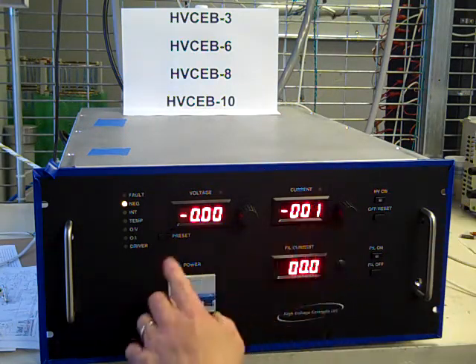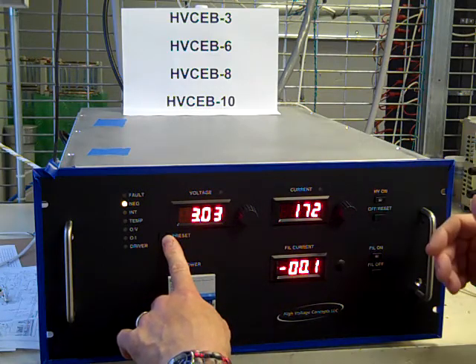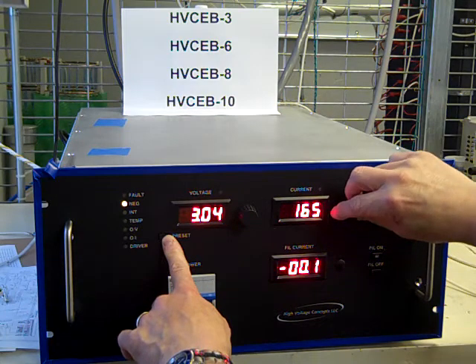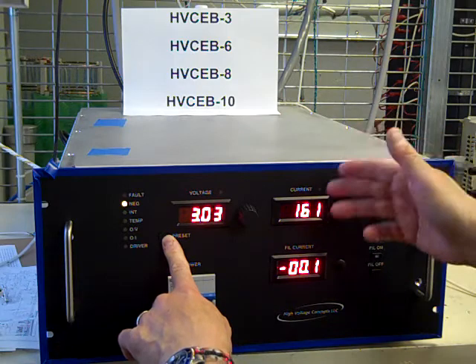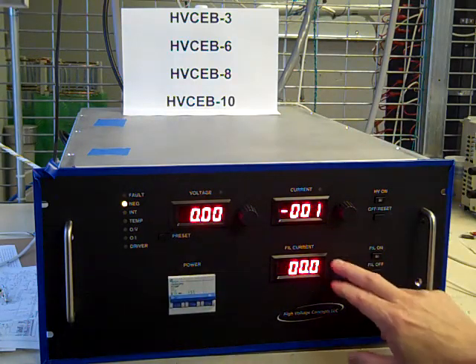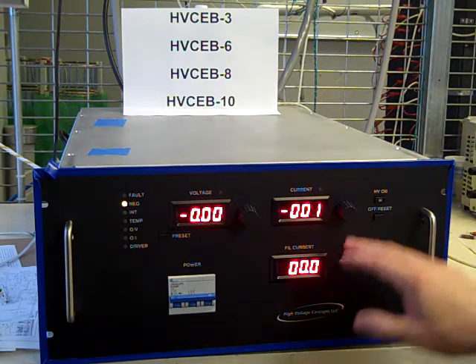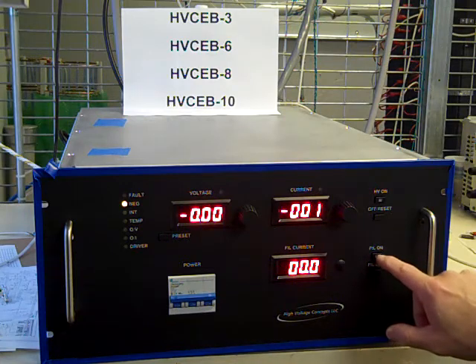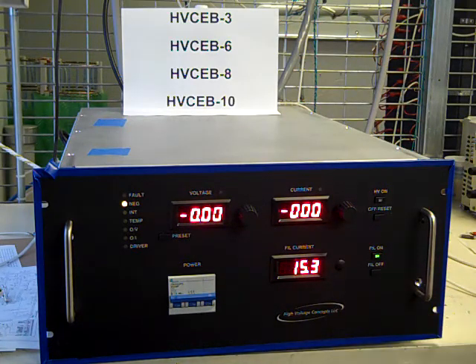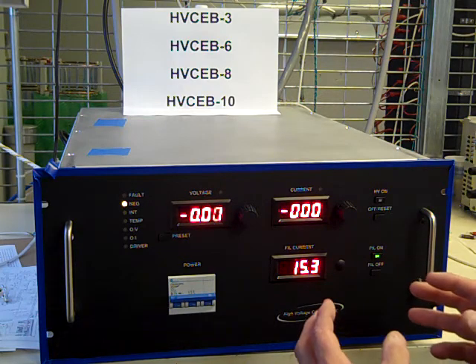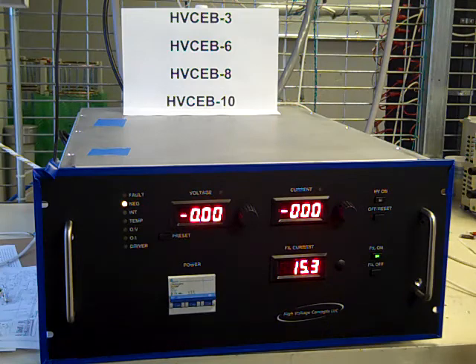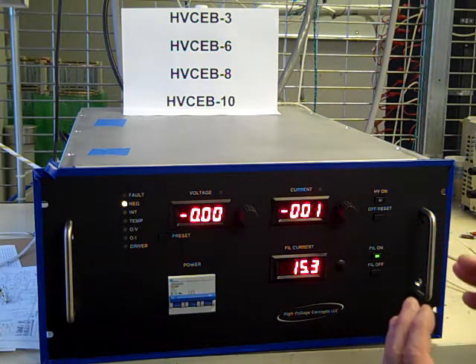And this is the current set point. This is how much beam current you want, and this is also adjustable, anywhere on this power supply up to 600 mils. Filament current has 3 regulation points. When you turn filament on, which we will do now, you can see there's approximately 15 amps there. This is what's called a standby or a preheat condition, and what this does is it turns on the filament just before high voltage, so that the filament itself in the gun is not shocked from being ice cold to going into regulation. It also speeds the entry point into the regulation because the filament is preheated.